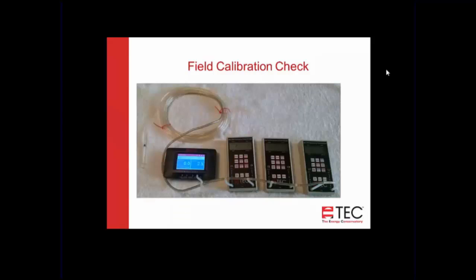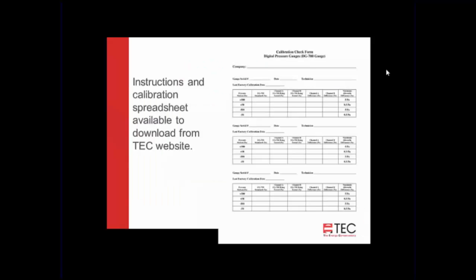So this is showing that procedure again with 4 gauges total. We're using the DG1000 as a master, and we're connecting to the reference on one of those channels, and we're comparing that with the 3 other DG700s. So the instructions on the website will include this calibration check form for your documentation. So you record the serial numbers and the date, the technician whose gauge that is, and the last factory calibration. And that factory calibration date will be on the sticker on the back of the gauge. So you're documenting that date of last calibration, as well as today's date when you're doing the field calibration check.